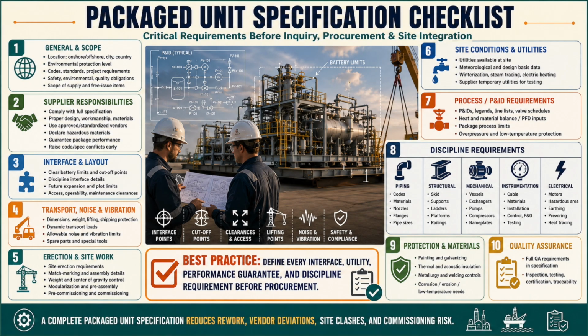List governing codes, project electrical specifications, motor specifications, and motor data sheets. Define hazardous area classification and the required protection concepts for all electrical equipment. Specify earthing philosophy, lighting scope, and the extent of supplier-provided earthing materials. Decide whether the package will be fully pre-wired to package junction boxes or wired at site. Full pre-wiring may reduce field labor, but only when cable routing, segregation, termination, and maintainability are properly engineered.